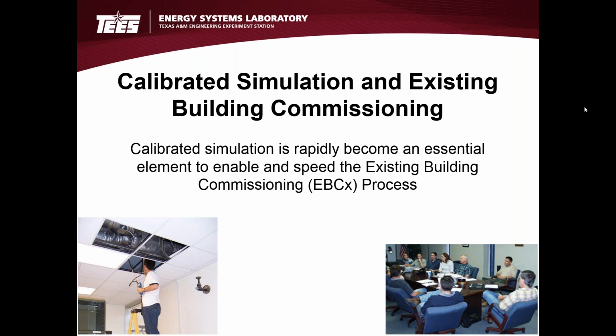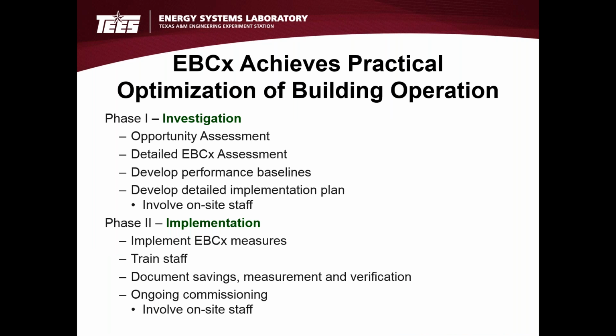And on this slide, I'm simply saying that calibrated simulation is rapidly becoming an important part of it. It certainly has not been a significant part of the commissioning process historically, but as the calibration process itself becomes either automated or nearly so, it becomes much more practical to use it when you're talking about doing something rapidly in the field.